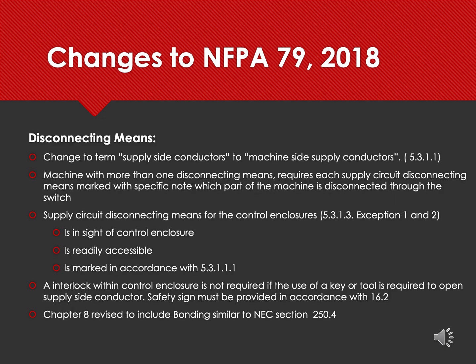This slide shows some of the changes addressed in Chapter 5 of NFPA 79 for disconnecting means. First things first, a machine is considered an individual unit in the context of the NEC, and so it must be supplied with a disconnecting means, period. All the terminology around the supply side conductors has been changed to machine side supply conductors.